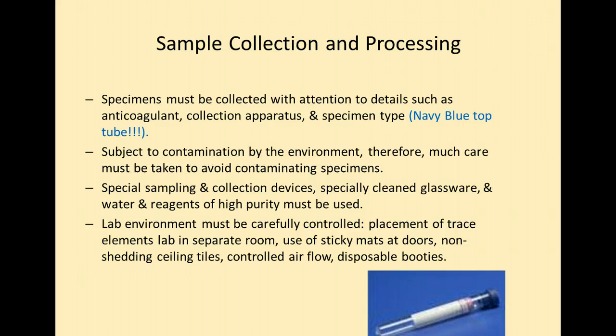The laboratory environment where this testing is done is very carefully controlled. They usually have sticky mats at the door, non-shedding ceiling tiles, controlled airflow, and disposable booties to make sure any dust particles that could potentially contain those elements cannot fall into your sample and affect the results.